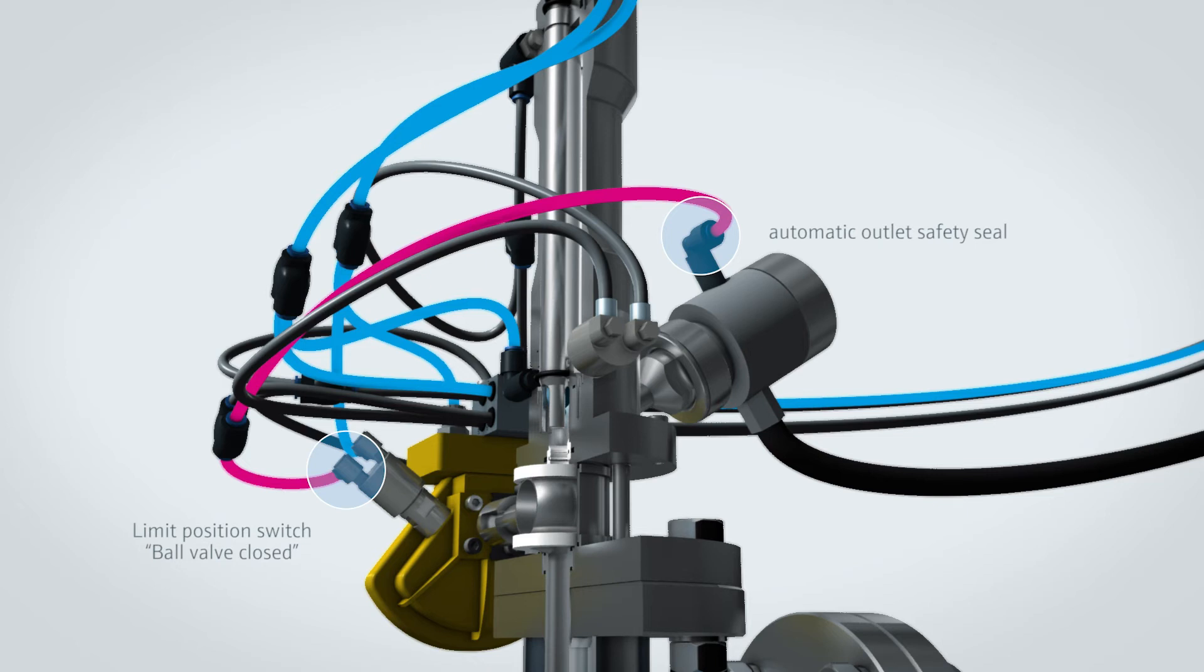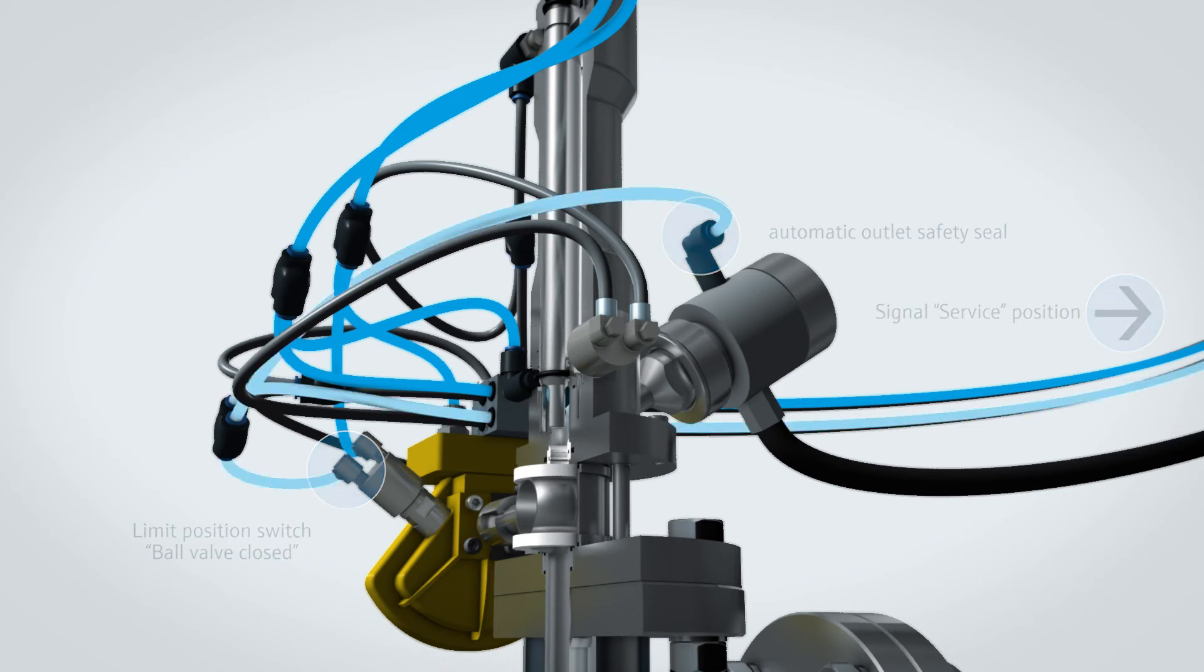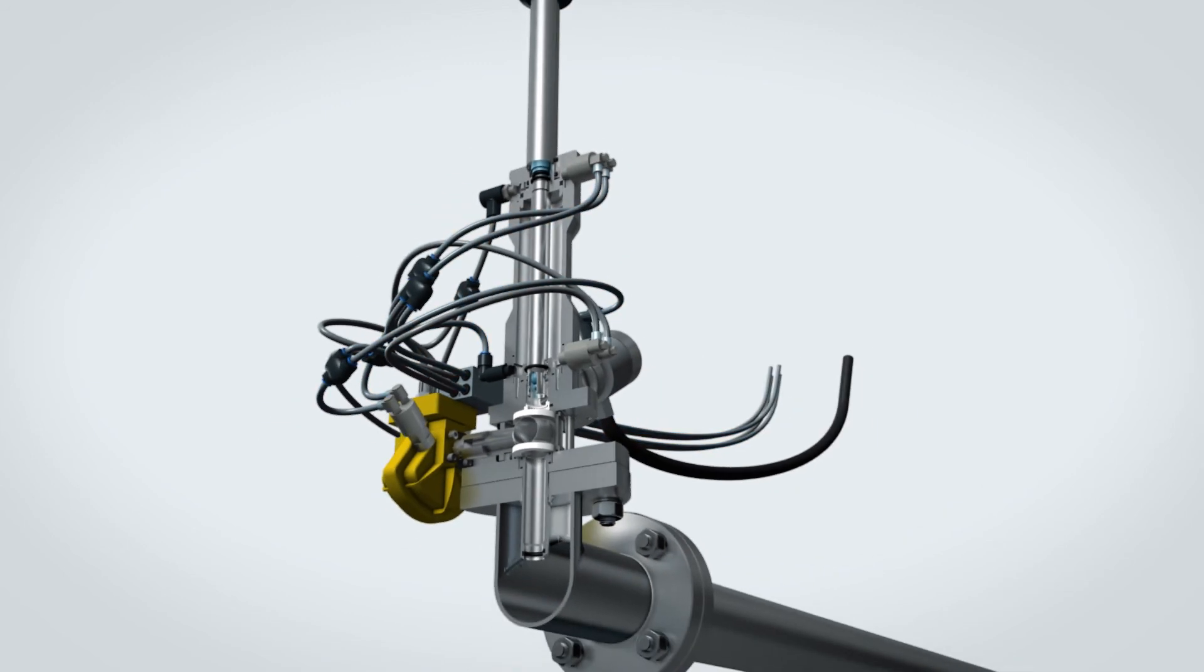In addition, a pneumatic or electrical signal can be output to indicate that the sensor is now in the service position. You can now remove the sensor or release the top part of the assembly from the ball valve in order to replace seals or perform other maintenance tasks.